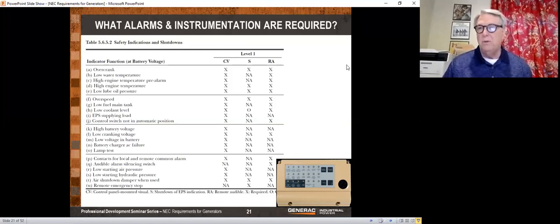They're pretty good. They're only, I'm guessing, like $400. So it's not a hugely expensive item. And they have lights for each one of these alarms in shutdown situations. So I told you some generators only have a malfunction light. Other generators will actually show you what's wrong, and the code actually requires that if it's a legally required or an emergency generator, not only do they have to have all these sensors there, but they have to show you which one of these things is causing the problem.